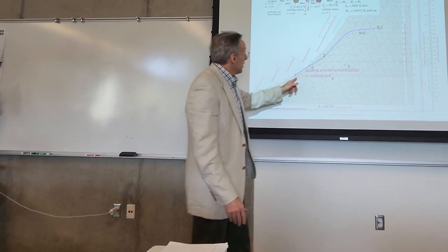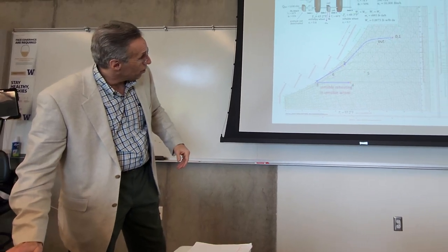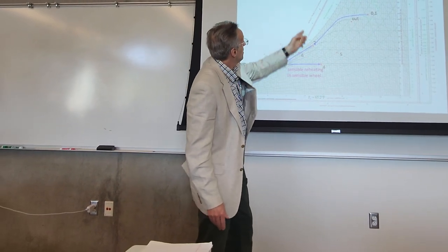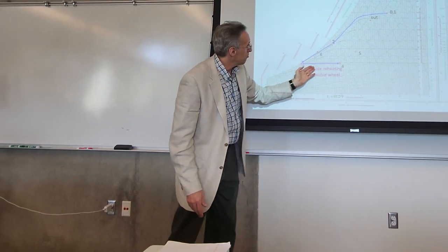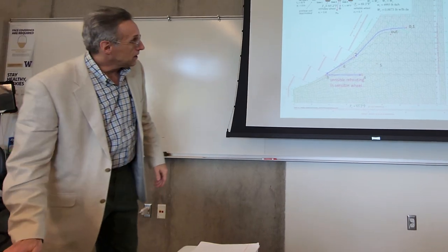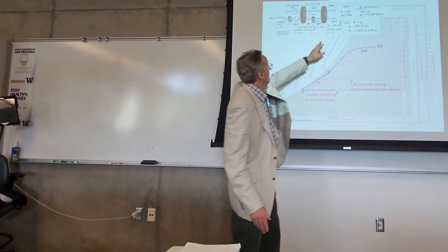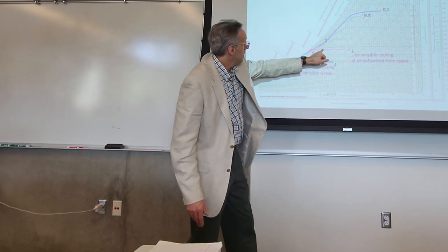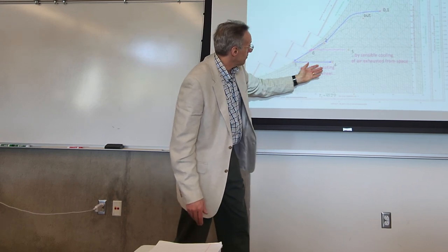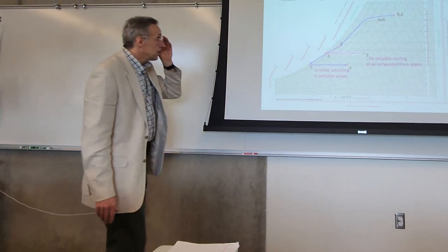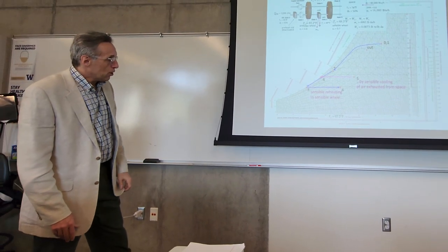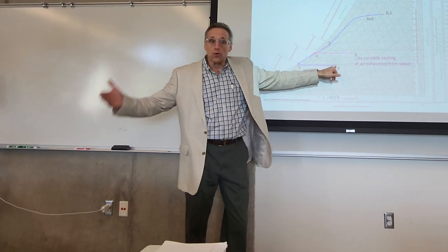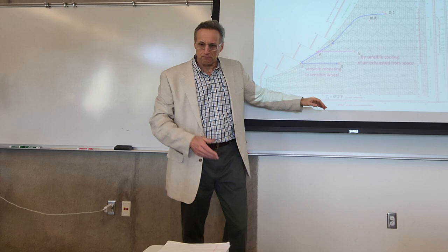Some other process. So we come off the cooling coil and then we go through, polish it up, make it a little more comfortable. Just sensible heating, so no change in moisture. It brings us up to 4. And we do that by taking our return air from the room, and it's warmer, so it's going to pass off some energy to the air coming off the cooling coil. And then this is the air that goes either into the space or it mixes with return air somewhere.